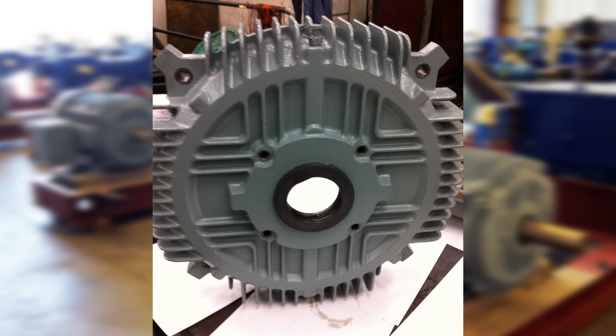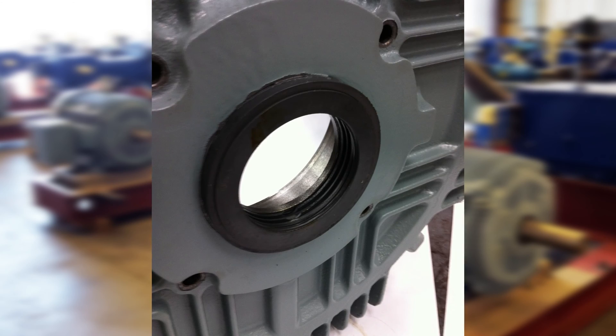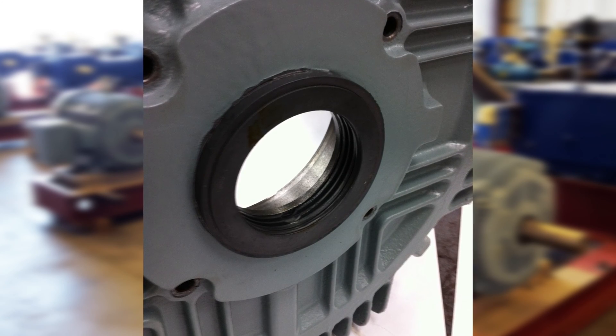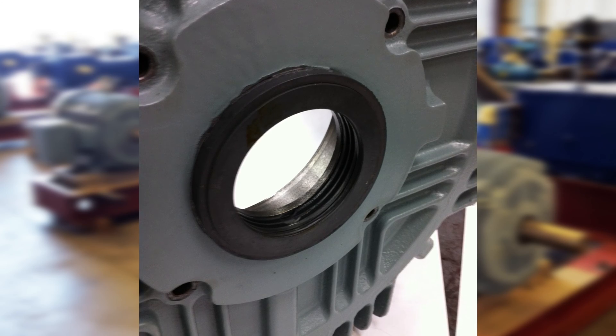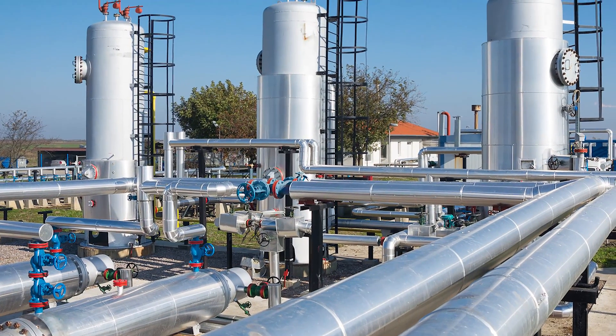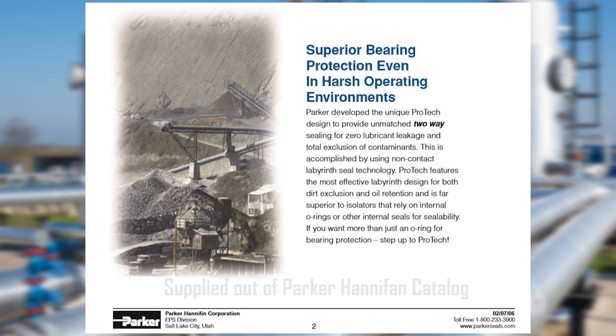The Hyundai IEEE 841 motor uses a Parker Hannifin ProTech Isolator. These superior seals are rated IP66 for dust and water exclusion, resistant to 160 chemicals versus 11 for only bronze. It is a true non-contact seal. It will not wear out and does not need to be lubricated.